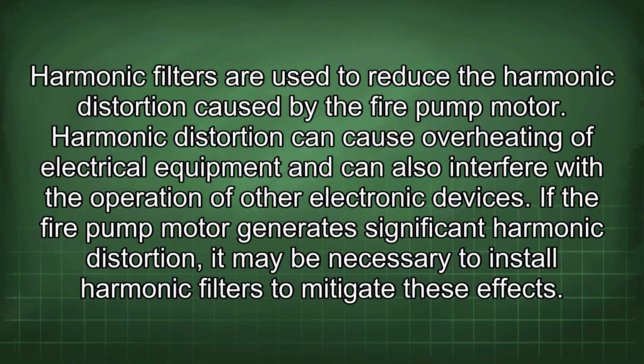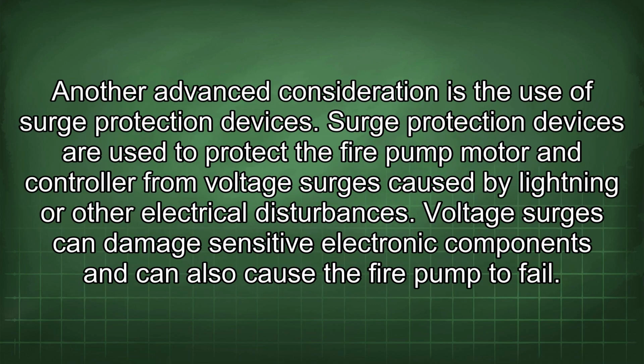Harmonic distortion can cause overheating of electrical equipment and can also interfere with the operation of other electronic devices. If the fire pump motor generates significant harmonic distortion, it may be necessary to install harmonic filters to mitigate these effects. Another advanced consideration is the use of surge protection devices.